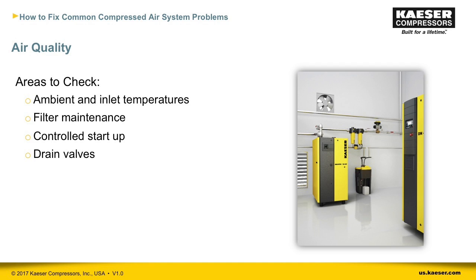Once you know what equipment you need to have the right level of air quality, here are some areas to monitor and check to ensure consistency. Ambient and inlet temperatures greatly impact dryer performance. That's why dryers have correction factors to help you properly size them. If your temperatures spike, your air treatment will not be able to effectively treat as much air. Make sure filters and dryers are sized correctly for the pressure and temperature of the system. Use the correction factors supplied by the manufacturer to ensure everything is properly sized. Consider worst-case conditions in the room where your dryer sits.